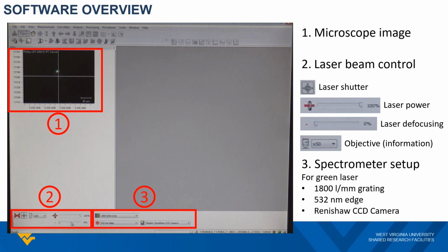Then there is another set of buttons that will allow you to choose the spectrometer parameters according to the laser excitation source. By default, we are using the parameters for green laser source. You will need to adjust those parameters when choosing a different laser source. Again, the operation of UV and IR laser will be covered in a separate training module.